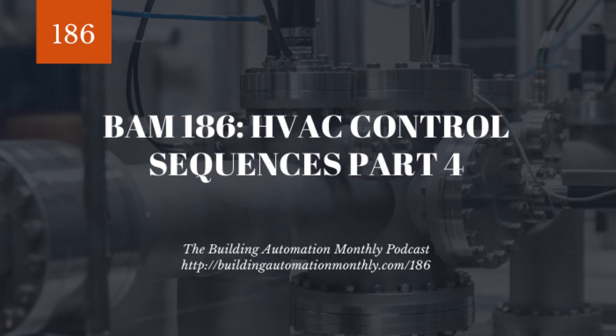All right, so that's pretty much it for a 100% outdoor air unit. Sometimes for 100% outdoor air units, you'll have an ERV, which is an energy recovery unit, and it could either be for humidity or for BTUs. For humidity, it's typically a wheel with desiccant on it or some other chemical, and it will reclaim moisture and then reintroduce moisture into the airstream, or remove moisture and introduce it to the exhaust airstream, just depending on what you're sequencing.